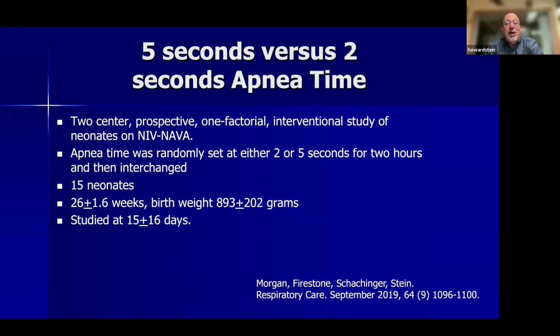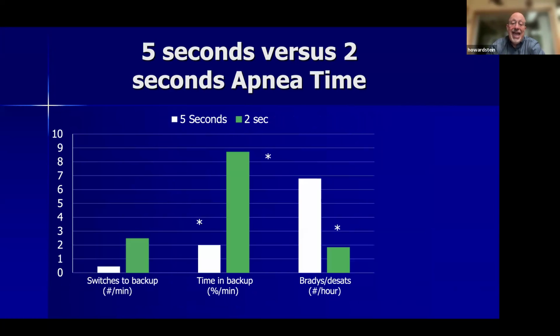We did a study where we looked at comparing an apnea time of 2 seconds to 5 seconds, and then we interchanged it, and we looked at the clinically significant events and what was going on with the babies. The white is 5-second apnea time. The green is the 2-second apnea time. You can see that with 5-second apnea time, they go into backup a whole lot less. Their time in backup is a whole lot less compared to 2 seconds.